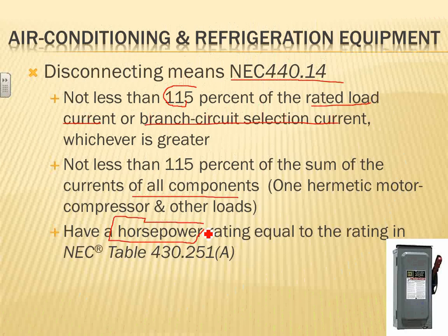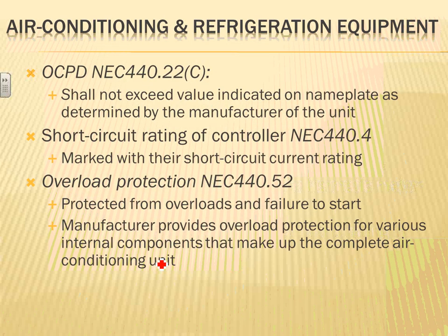Then you have to size it based on the locked rotor current equal to the rating that's coming from right in here, amp-wise. So it has to be horsepower rated to handle the amps, as full load amps as well as locked rotor current amps. And I have a couple of examples for these.